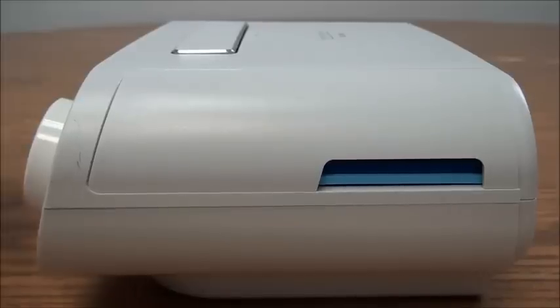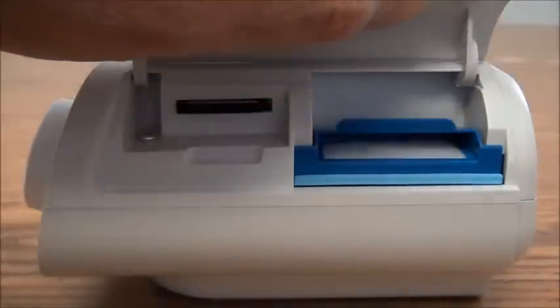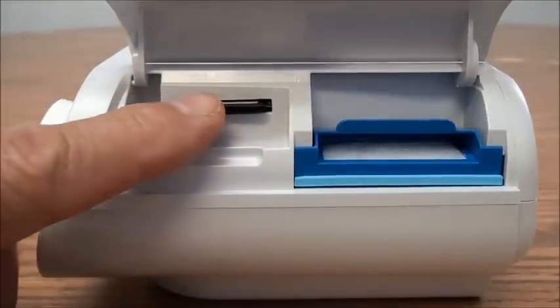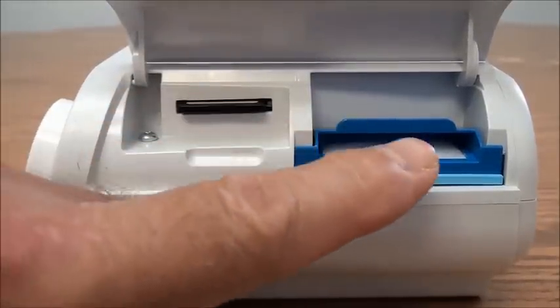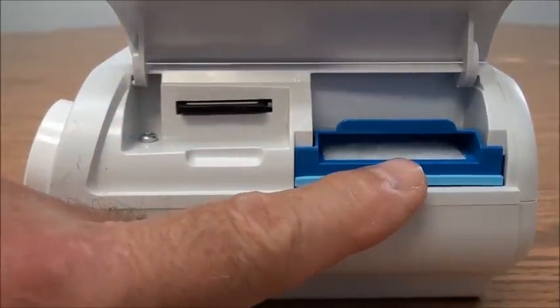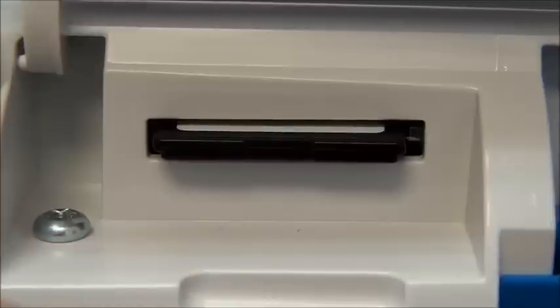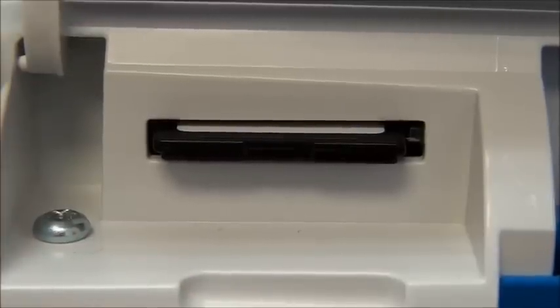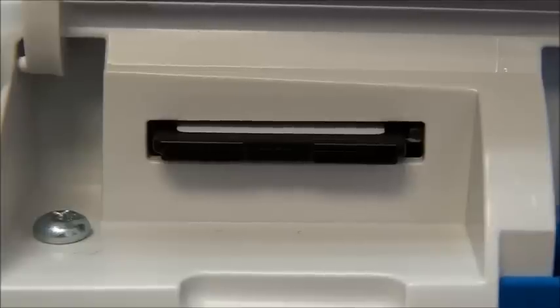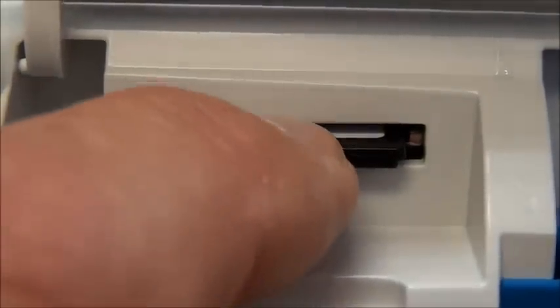On the right side of the machine, we have a door that can be lifted, and then we can access the SD card and the filter for the machine. The SD card records your sleep data. It is used to prove that you are compliant with the machine. The card can be removed by depressing the card and then pulling it straight out.